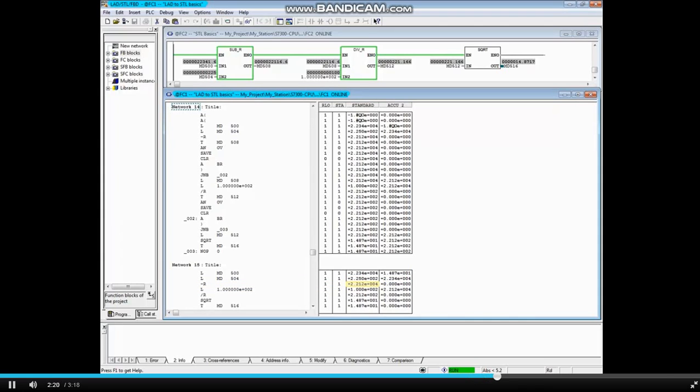The result is sitting in Accumulator 1, so there's no need to store it anywhere. The real number 100.0 is loaded. The divide as real numbers instruction divides the previous result by 100 and places the result, 2.212 times 10 to the 2nd power, in Accumulator 1.